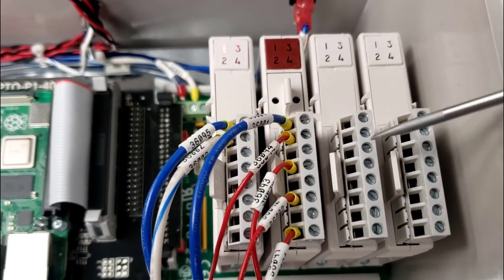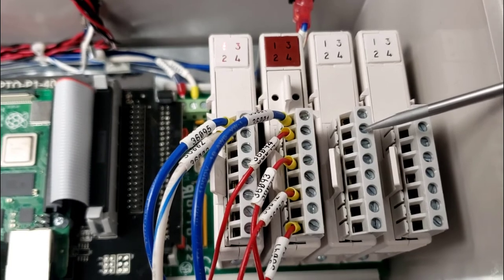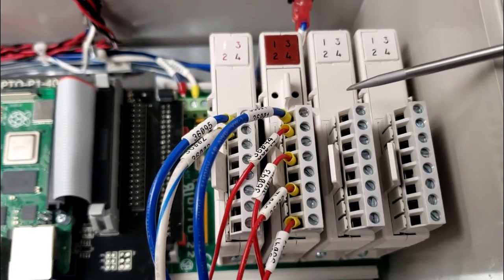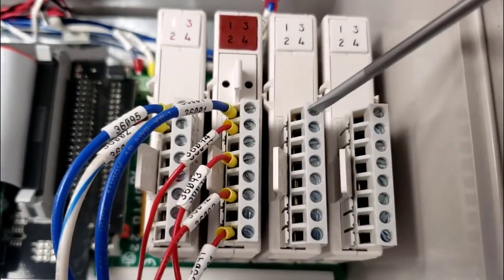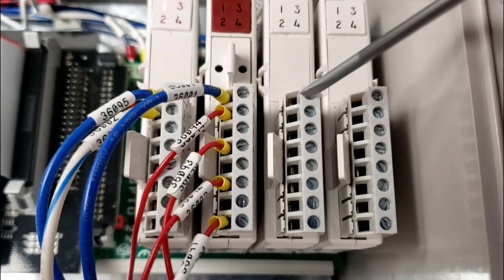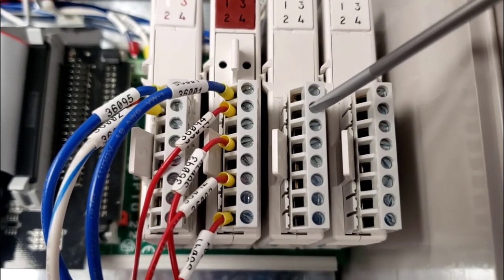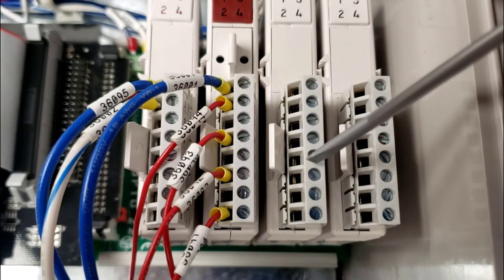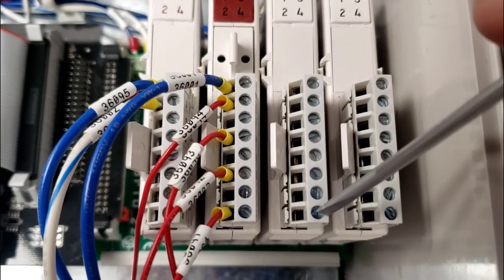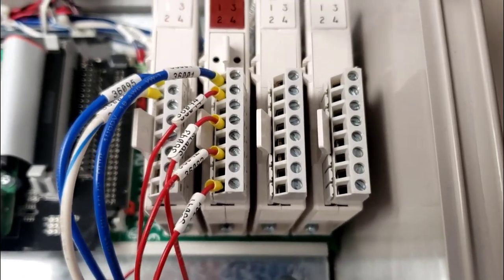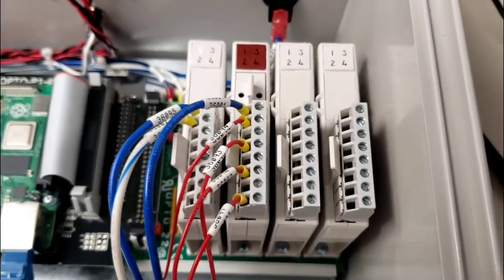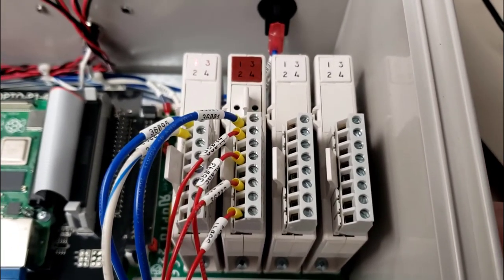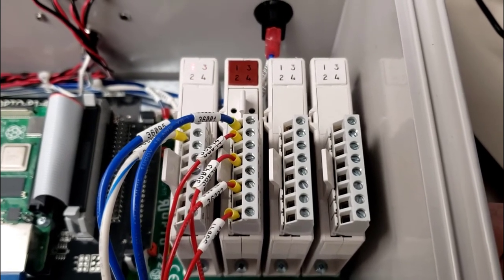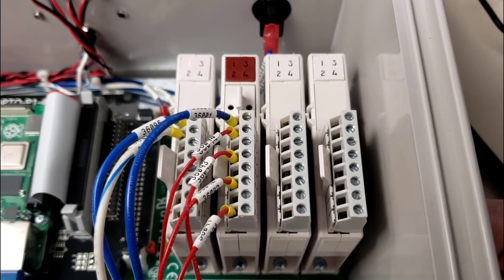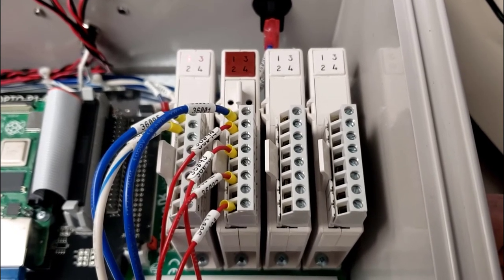So you have the ability to bring in 8 signals, so 8 pairs of wires coming in, 4 on each optocoupler. This would be module 1, this is module 2, and this is port 0. Then port 1, port 2, and port 3. What I'm currently using here is set up for 24-volt DC inputs, but this can be set up for other voltages as well: 120, 240-volt AC, higher level DC as well, and lower even if needed.